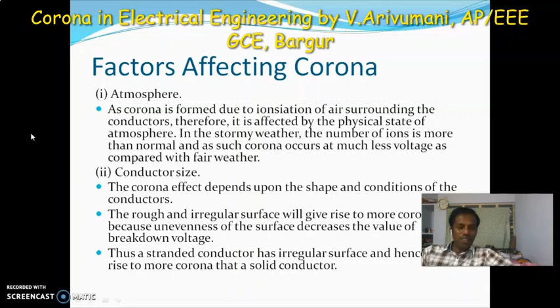So in transmission lines, we are using the stranded conductor because of the uniform electric field compared to the solid conductor, but corona will occur in a stranded conductor easily compared to the solid conductor because of the irregular surfaces. So a regular surface will create lesser corona compared to the stranded conductors.